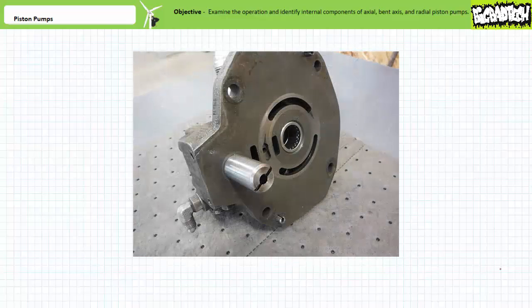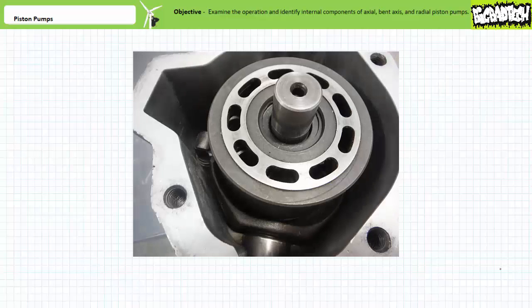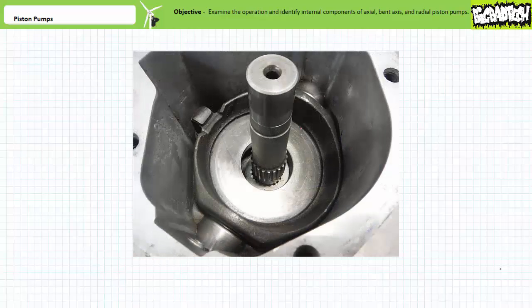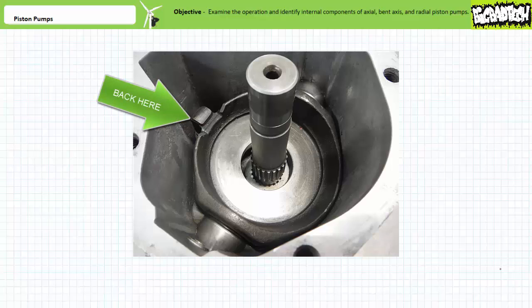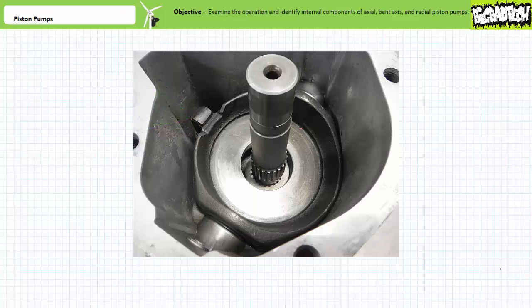Here's the internal workings of yet another variable displacement axial piston pump that employs a slightly different method of varying the swashplate angle. One half of the housing features a piston. The other half features a piston and piston block sitting on top of the swashplate. When we remove the pistons and piston block, we can see the swashplate being acted upon by a spring. The piston in the other half of the housing counteracts the spring force. When the two opposing forces are equal, the swashplate is held flat and flow is at a minimum. When the spring exerts more force, the swashplate is held at an increasing angle and flow increases.